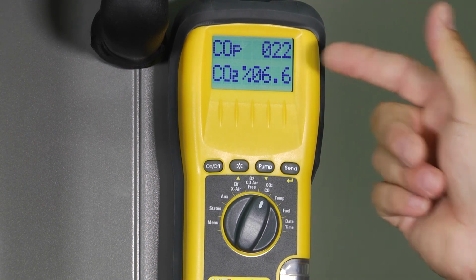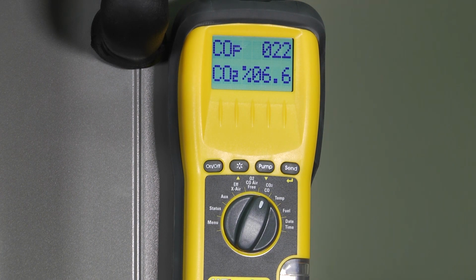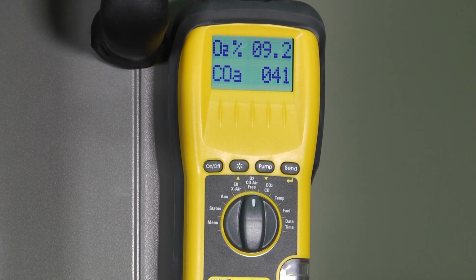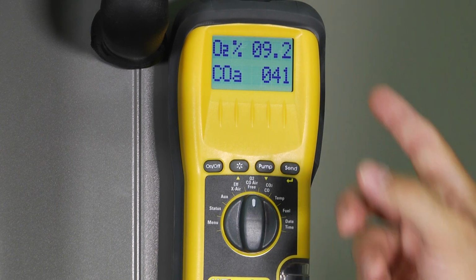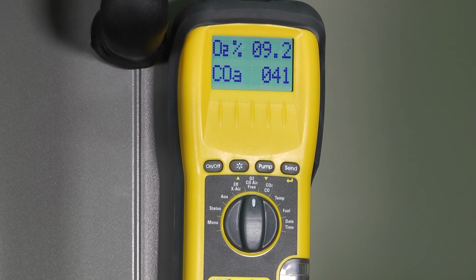But look at my carbon monoxide, that doesn't take into account the excess air that's inside of it. I'm at 22 here, but my air free sampling, when the combustion analyzer does that calculation for me, I can see that I'm much higher at 41, 42 parts per million. So again, still well below what we consider acceptable.